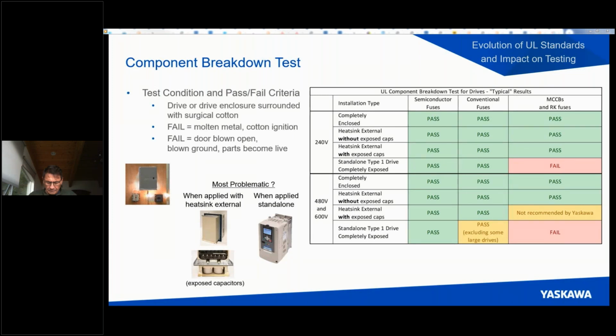Across the top from left to right, we have semiconductor fuses, which are the fastest acting and offer the best protection. In the next column, we have conventional fuses such as Class CC, J, or T, and these are also adequate protection in many cases. And then in the far right-hand column, we have molded case circuit breakers and RK fuses, which are the slowest acting devices and thus have more limitations of use. Now, based on what we have just learned about 240 volt drives, you'll notice there's only one case in which any of these devices won't protect a 240 volt drive, and that's the combination of a standalone drive with a circuit breaker or RK fuse.